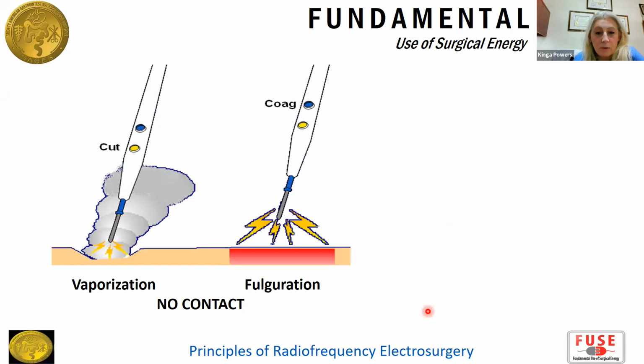In the non-contact modes, there's vaporization, which uses low voltage outputs such as the cut mode, and fulguration, which is basically a process of high voltage where tissue is superficially coagulated but with a wide spread, because there is elevation of temperature on the coag mode to very high degrees Celsius, so over 100 degrees Celsius.